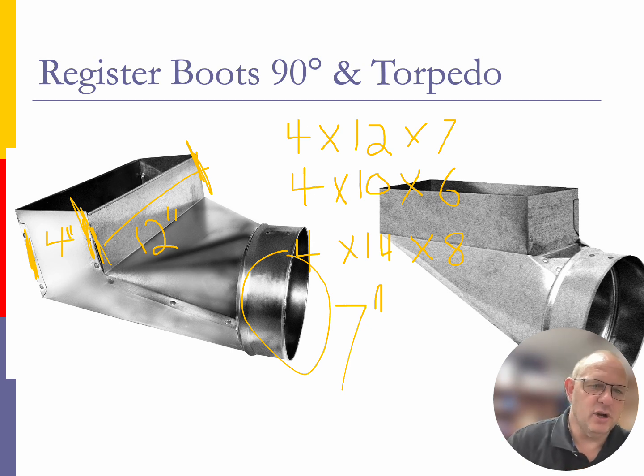That our sections are 4 by 12, you're going to have a 7-inch pipe. 4 by 10, you're going to have a 6-inch pipe running into it. And a 4 by 14, you're going to have an 8-inch pipe running into that. And that's all about air volume or CFM volume coming out of that register. But these are your 3 common sizes that you're going to be seeing for your ductwork. They do make other sizes that are out there, but this is a register boot that's going to be fitting in there.